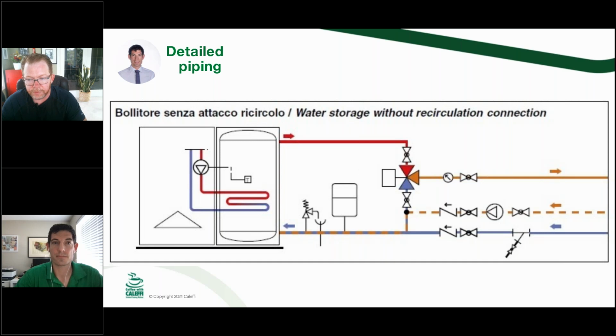One of the other questions that comes up as well, Max, is with the recirc creep again. Would thermal traps help or hinder from the standpoint of recirc creep, or should we worry about it at all? So it's a good piping technique to incorporate, but I would use one of these two piping diagrams that we send, regardless of the trap that you create with the piping. The best protection is just going to be to have the ability to close that hot 100%. Is probably the best way around all this.